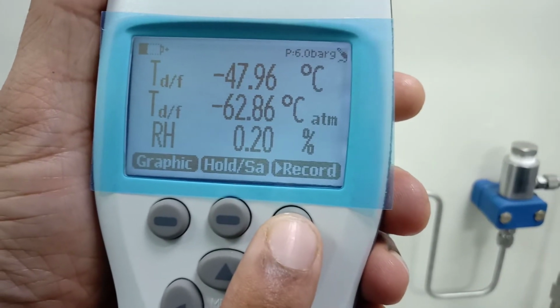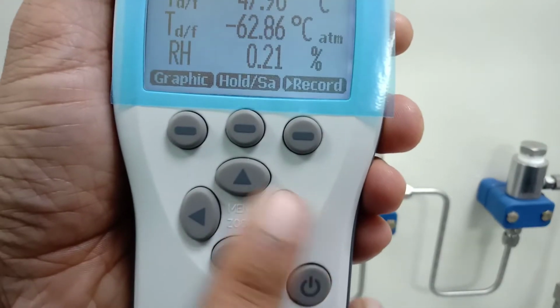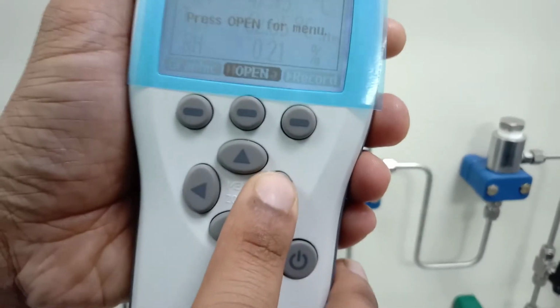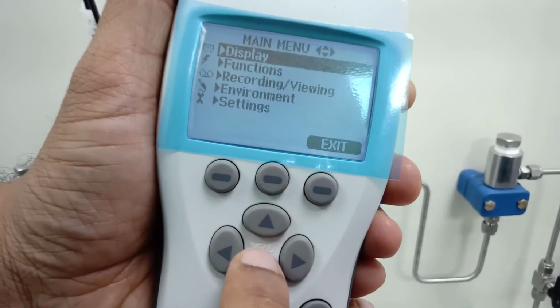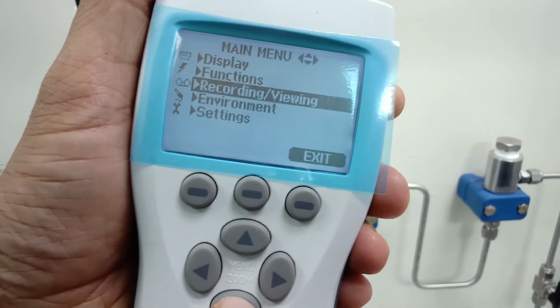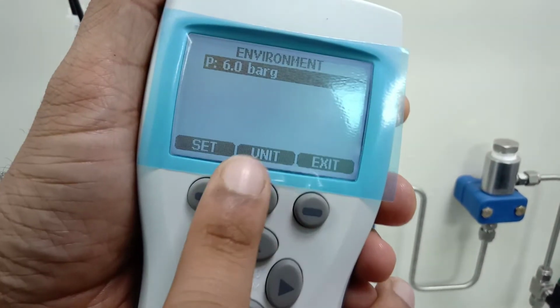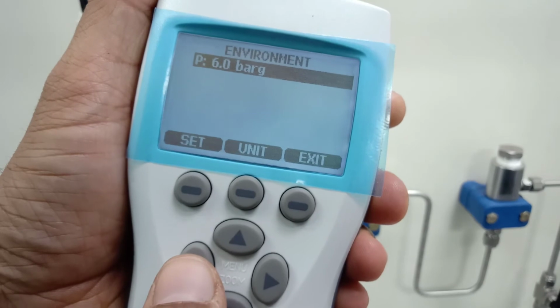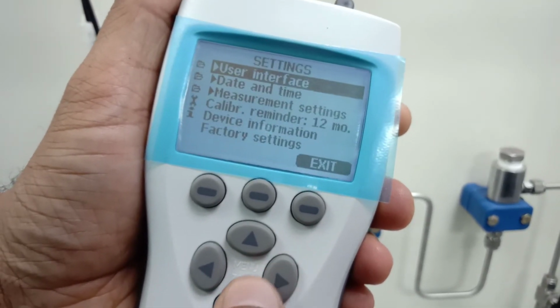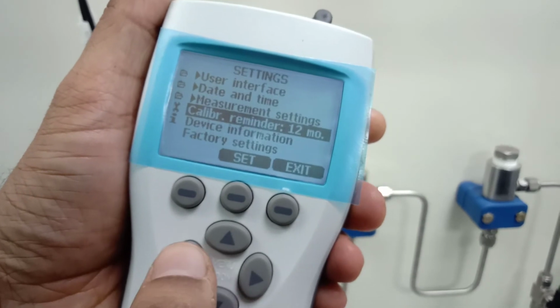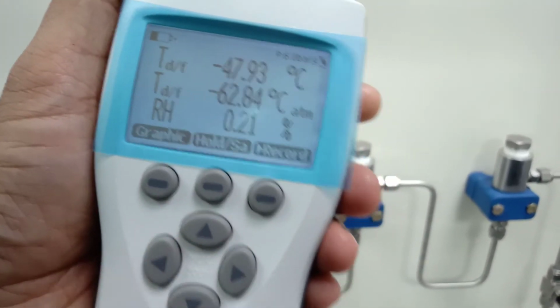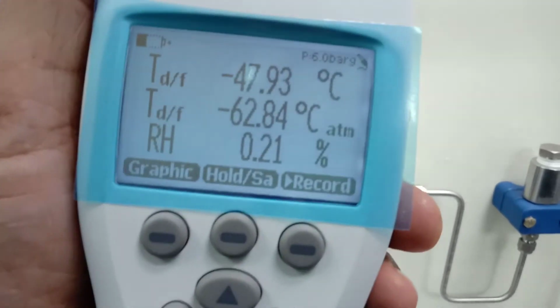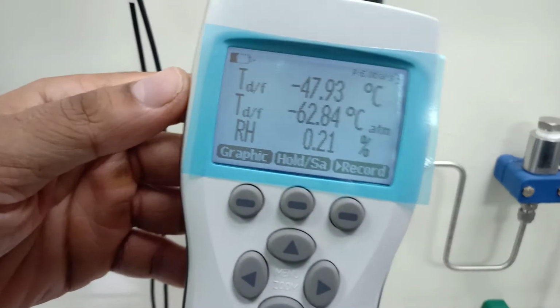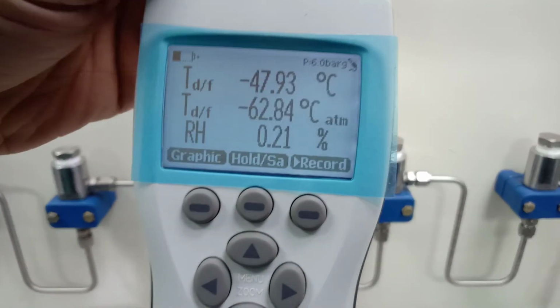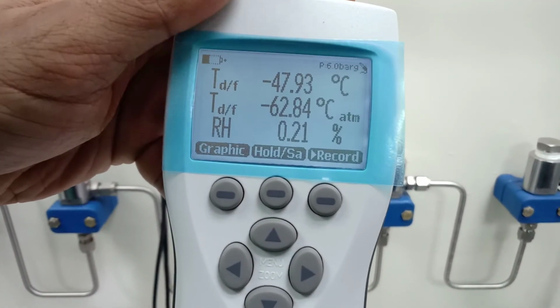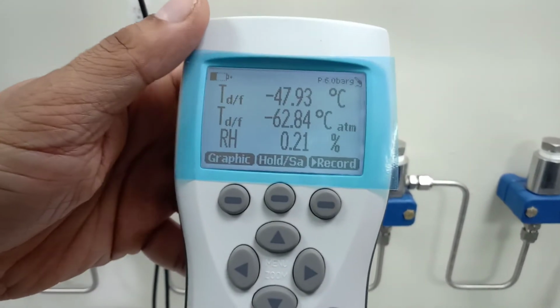The data can be recorded. You can hold very easy. Any of the buttons can be used to go to the menu, open, and then you can display functions, recording. You can view the recorded data. You can change the environmental settings, in which in this case where you can change the pressure. You go back, settings, date and time, and these are the other settings. So we get the dew point, and it will change according to the conditions within no time. So the response time is about 30 to 45 seconds. You get the real time readings.